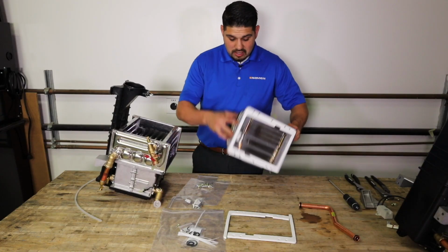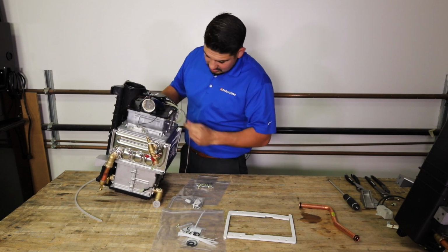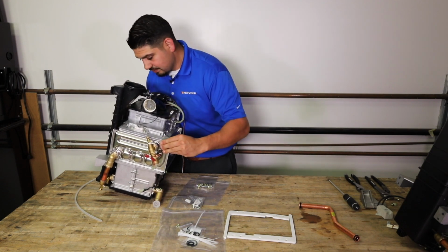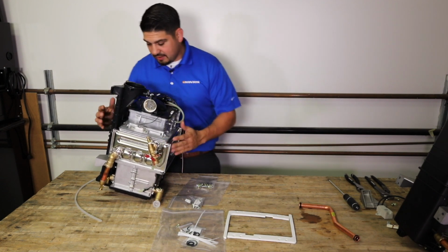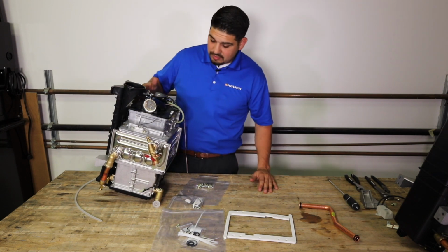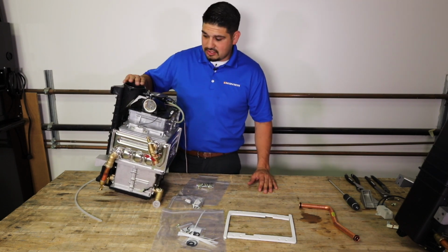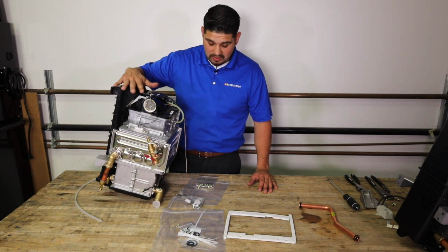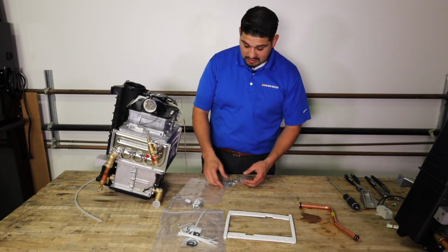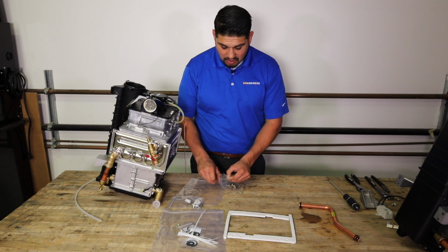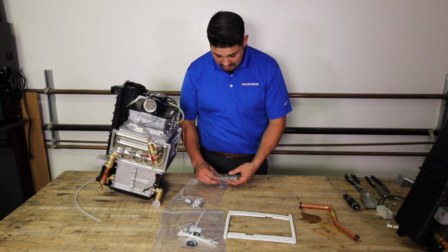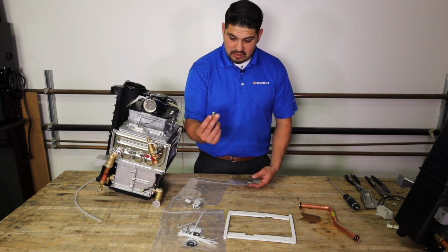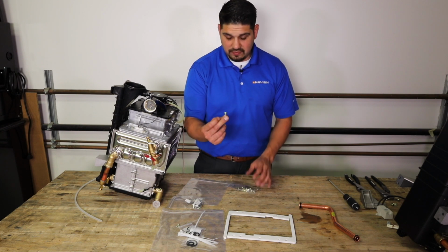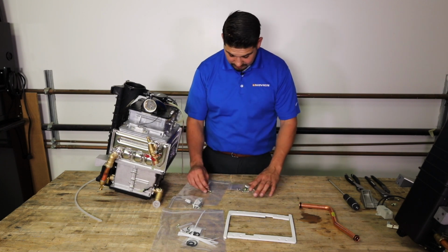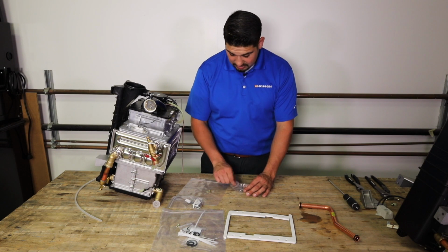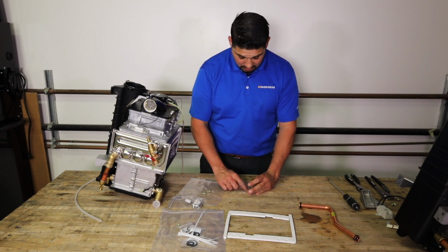So we're going to go ahead and put our new burner. And again, as a reminder, this center screw hole in the back of the burner no longer exists. It's just too hard with the exhaust and everything in the way, so it's not going to be there anymore, so we're not going to have to worry about that. Now in the hardware provided for us, there's these burner screws. They have a flat washer. There's only a few of them, so they're kind of unique. The washer's built into the head. We're going to go ahead and pull those out.